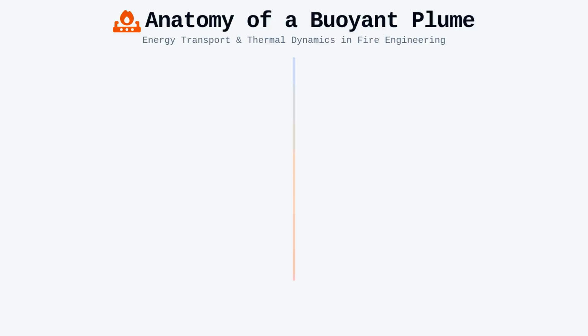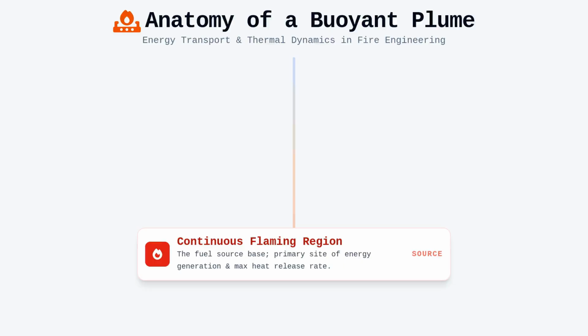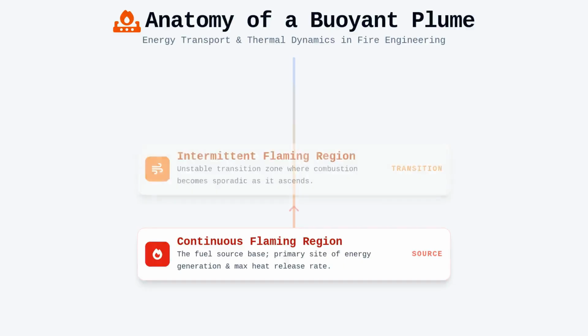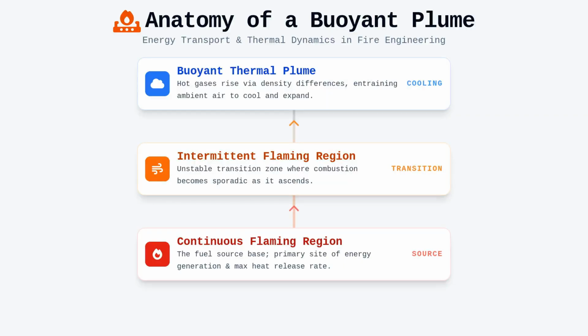A fire plume is essentially a turbulent buoyancy-driven flow where the combustion products are accelerated upward due to the density difference between the hot gases and the cooler ambient air. As these hot gases rise, they pull in or entrain surrounding air, a process that determines both the total mass flow rate and the cooling profile of the plume. We generally categorize this anatomy into three distinct zones: the continuous flaming region near the base, the intermittent flaming region above it, and the buoyant thermal plume region.